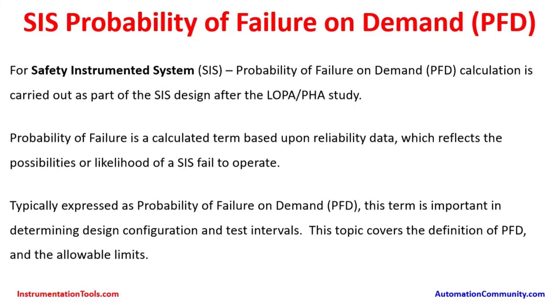Probability of Failure is calculated based upon reliability data which reflects the possibilities or likelihood of a SIS failing to operate. This is based on any possibility or likelihood that a particular component can fail to operate. Typically expressed as Probability of Failure on Demand, this term is important in determining the design configuration and test intervals.